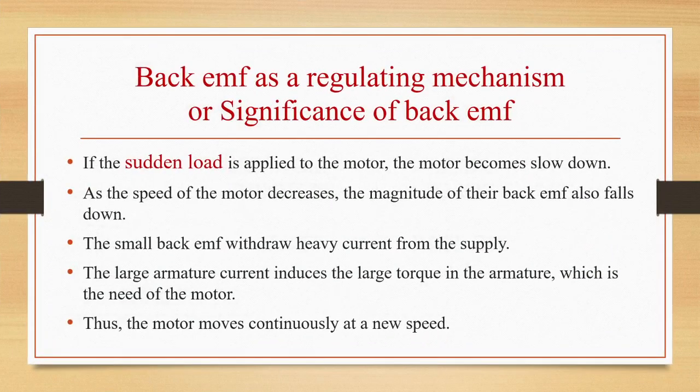Second one, if a sudden load is applied to the motor, it will become slow. As the speed of the motor decreases, the magnitude of the back EMF will also fall. Small back EMF will draw heavy current from the supply, and large armature current will induce large torque in the armature, which is the need of the motor. So the motor will move continuously at a new speed.